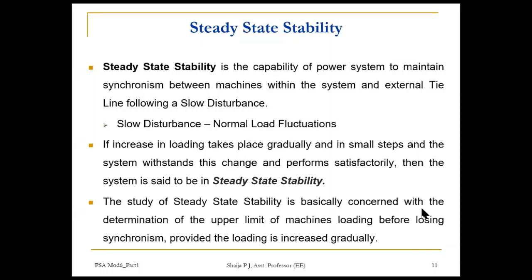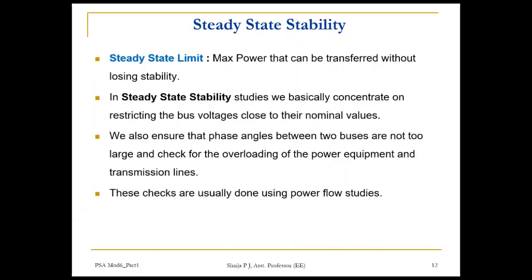The study of steady state stability is concerned with the determination of the upper limit of machine loading before losing synchronism, provided the loading is increased gradually. The steady state limit is the maximum power that can be transferred without losing stability. We concentrate on keeping bus voltages close to their normal values, ensuring phase angles between two buses are not too large, and checking for overloading of power equipment and transmission lines. These checks are usually done using power flow studies.